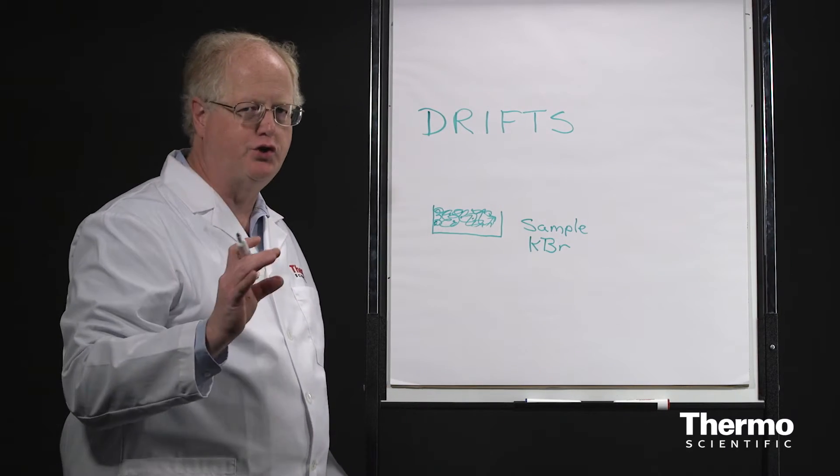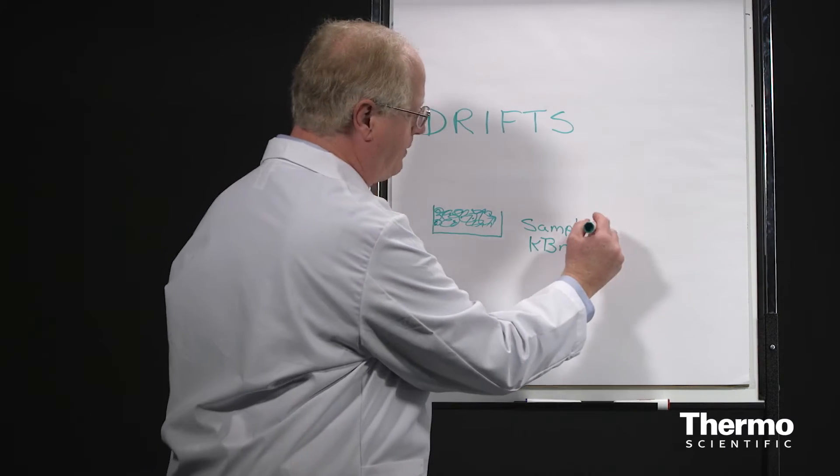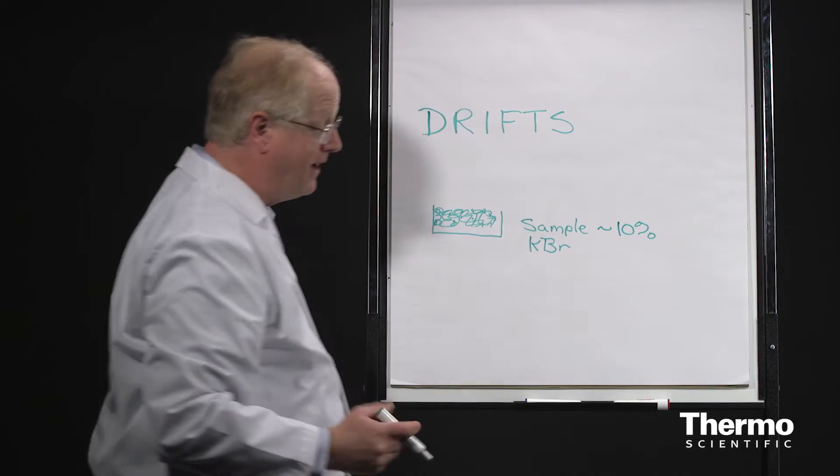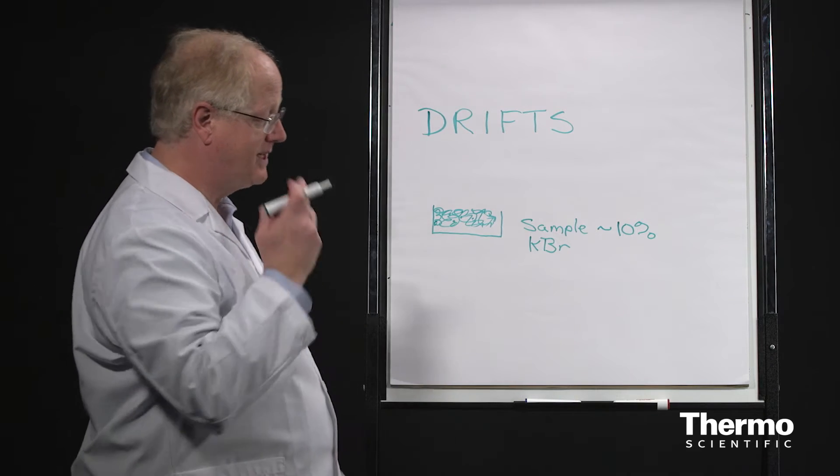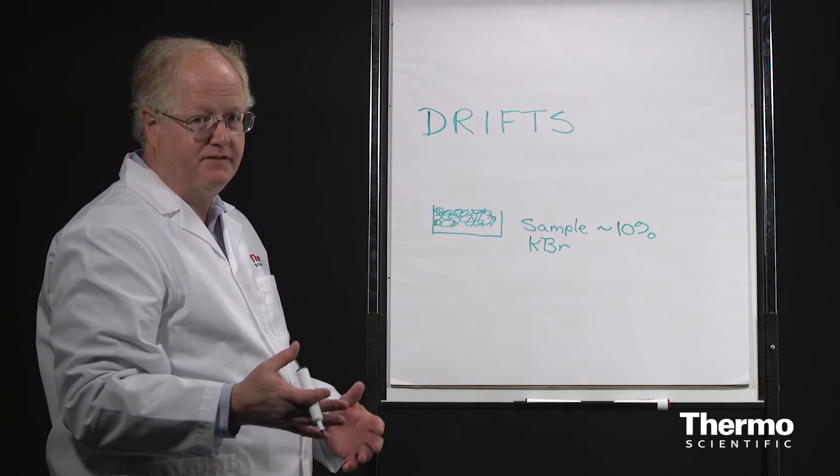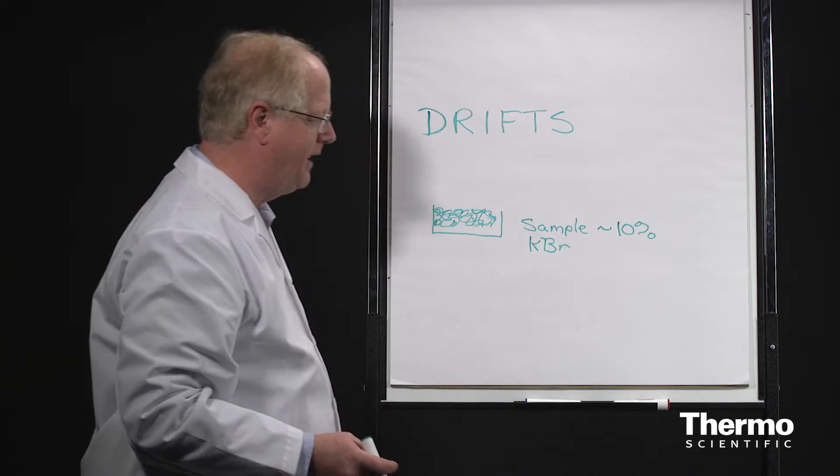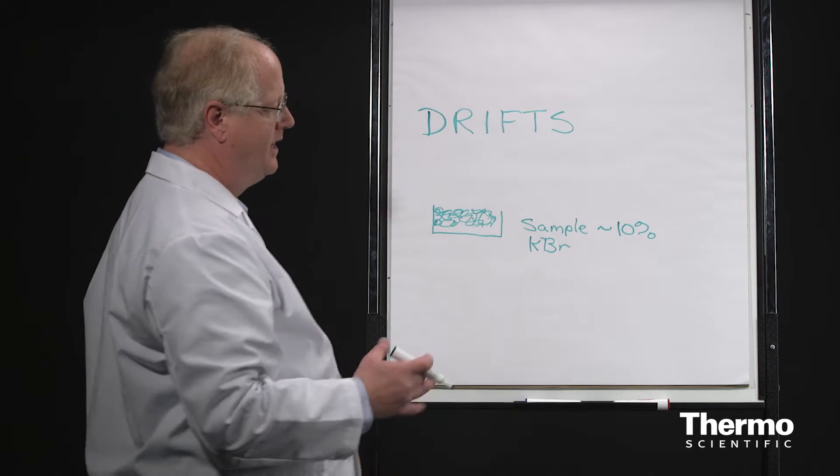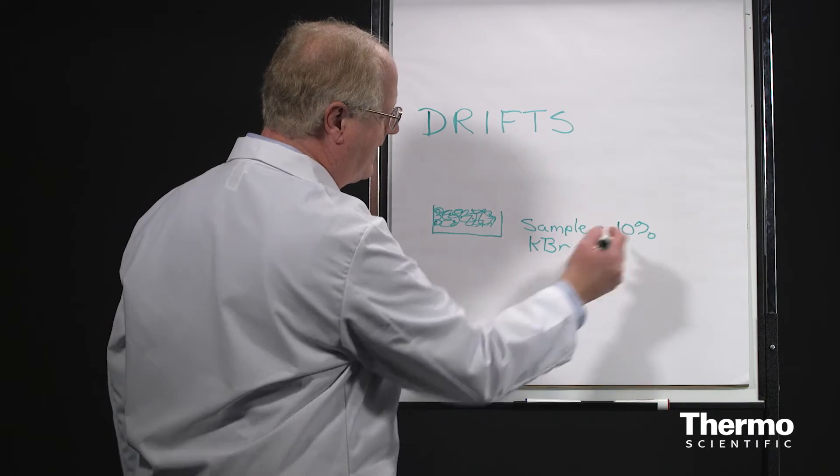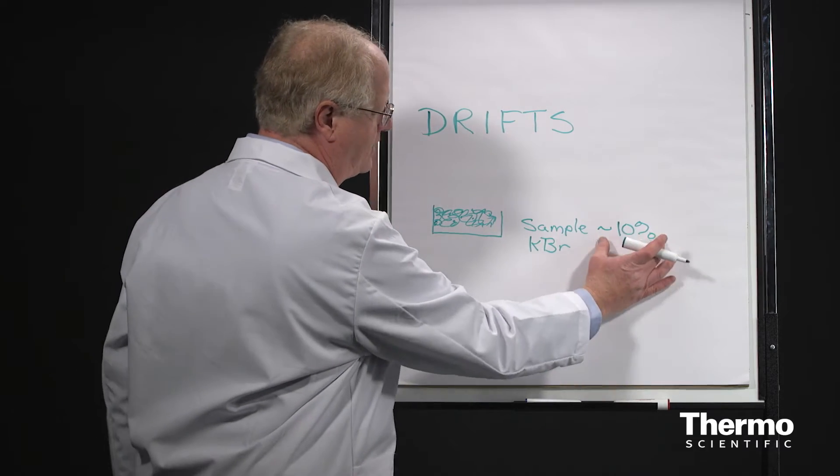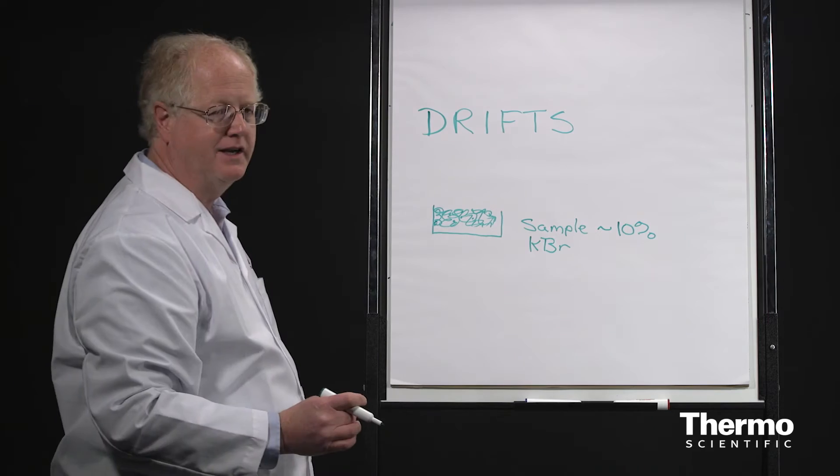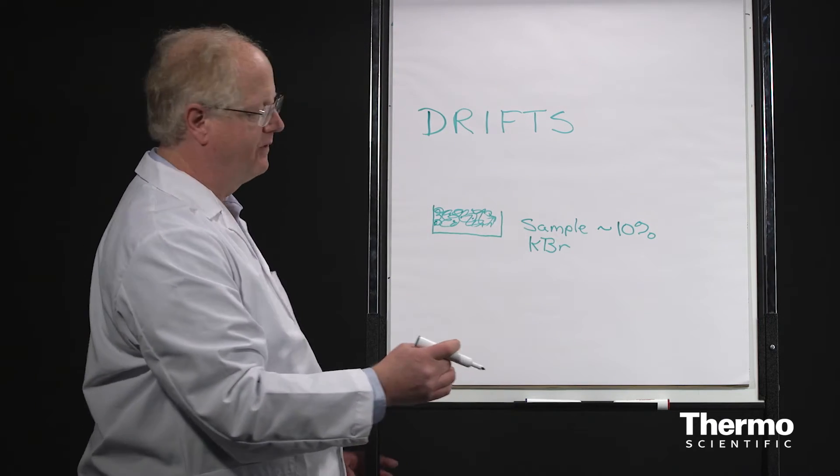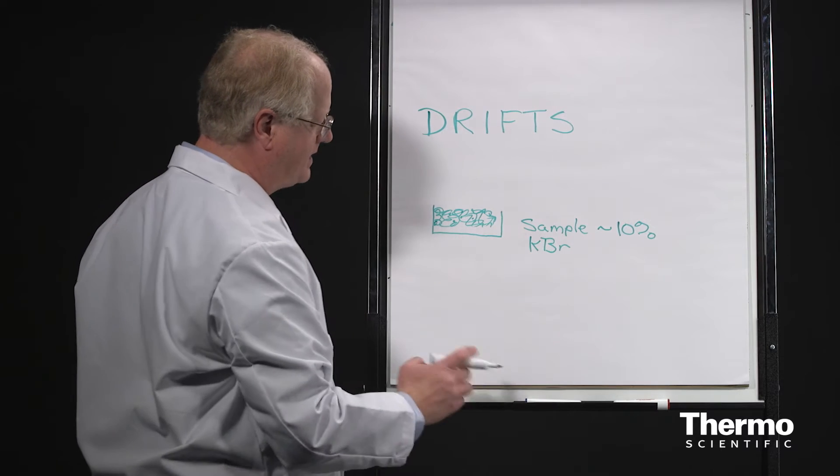Now, in order to get a good drift signal, you're going to want the sample to be around 10% or maybe even less. One mistake people make is they think a little bit of sample must be good, so more must be better. It isn't, because the sample will become totally absorbing. So you want the analyte to be not the main constituent. It's KBr powder. Sometimes we use diamond powder for various reasons, but KBr is easily the most common.